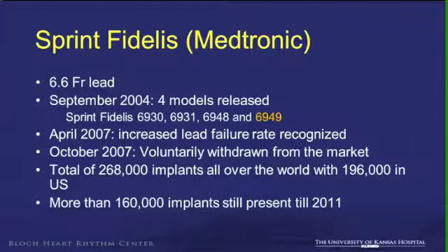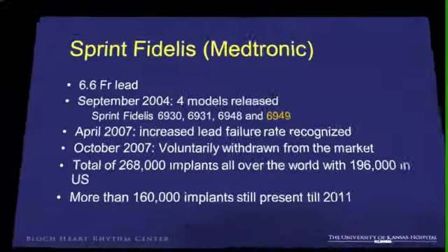So it was one of the smallest leads at that point of time, and a lot of leads were implanted. In April 2007, there was a confirmed recognition of increased failure rate, and in October, it was voluntarily withdrawn from the market. About 268,000 implants all over the world, with about 196,000 in the US. In early 2011, there were still 160,000 leads still implanted in patients. At this point of time, that number is significantly less.